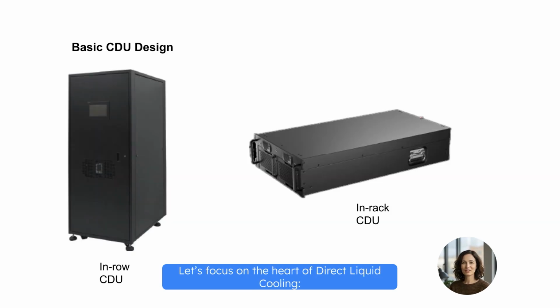Let's focus on the heart of direct liquid cooling, the CDU, liquid-to-liquid coolant distribution unit. As engineers, we define this as the hydraulic separation point. It isolates the rougher facility water system, FWS, from the precise technology cooling system, TCS. Think of the CDU not just as a heat exchanger, but as the brain of the loop. It regulates flow and pressure to protect the cold plates inside the servers.